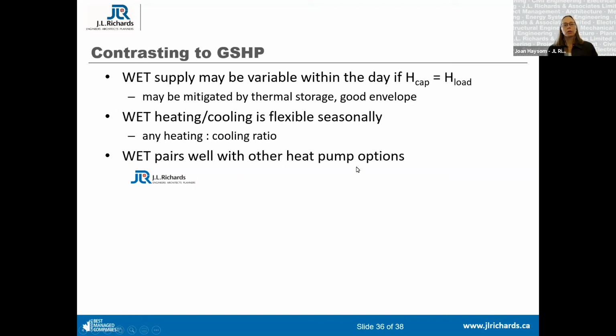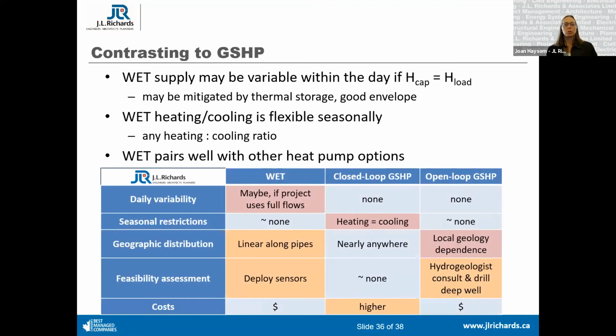I wanted to compare it to other heat pump options, so here's my little table - the wet system, a closed loop ground source heat pump, and an open loop ground source heat pump. Let me walk through this. The variabilities are different between these three technologies. With a closed loop ground source heat pump, you have to balance the heating and cooling over the season, or you're creating a net temperature change in the ground below.